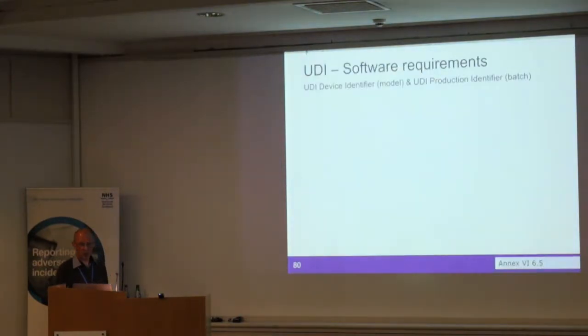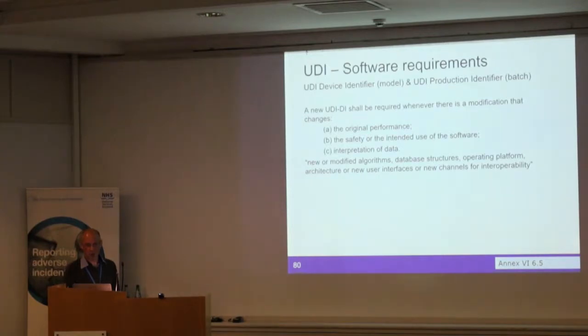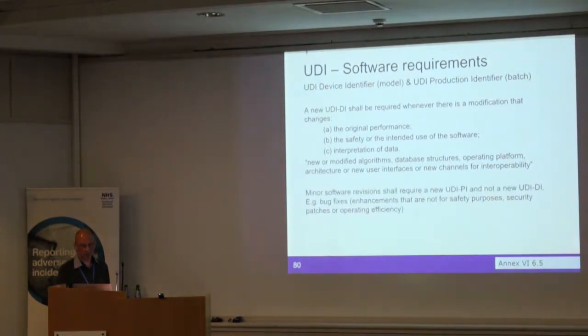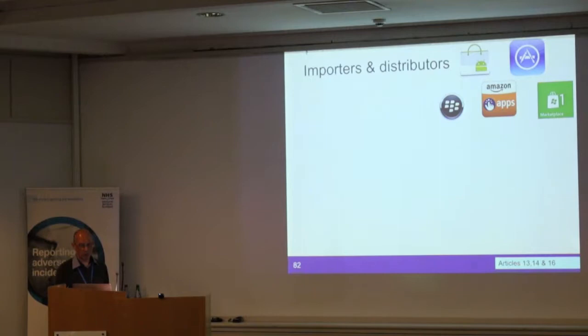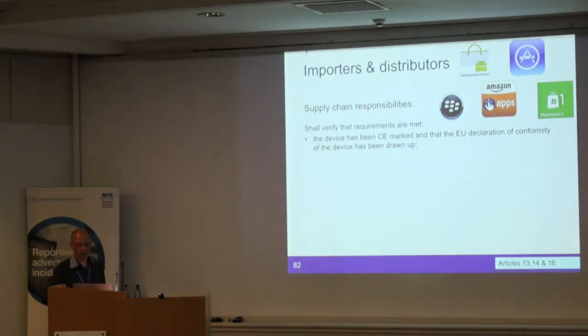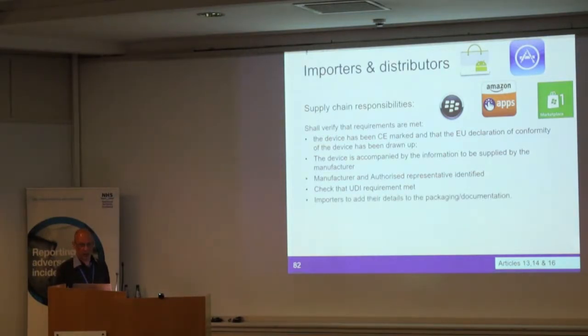The unique device identifier will also apply to software. So where there are changes to performance, safety of the software, or how the software interprets data, we'll need a new UDI device identifier number. Minor modifications will just require a production identifier number change. There'll also be requirements for importers and distributors, so app stores. They should be or will be checking that software has been CE marked, there's a declaration of conformity, the device is accompanied by all the information needed, that a manufacturer and authorised representative is identified, UDI requirements are met, all the contact details are there, and if they don't believe a device is in compliance, they will need to contact us and report it to us.